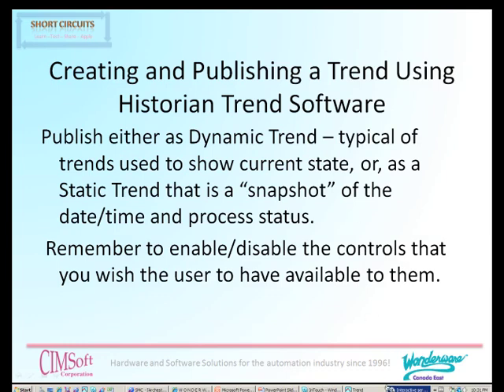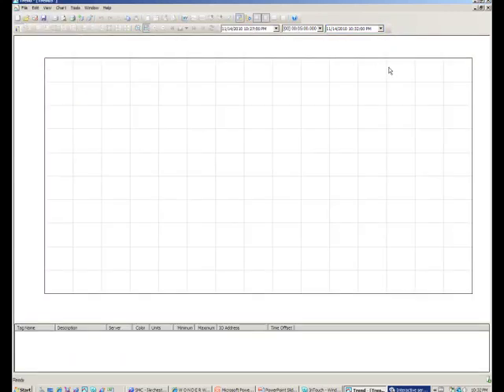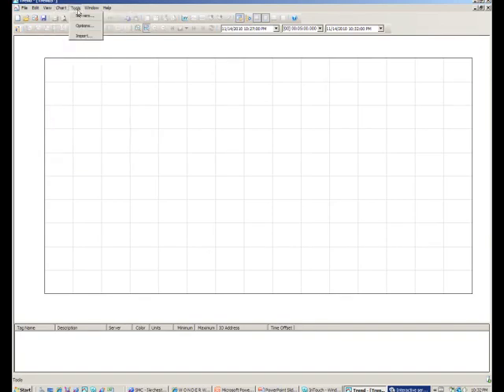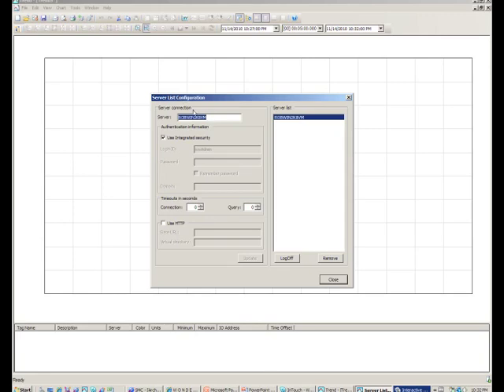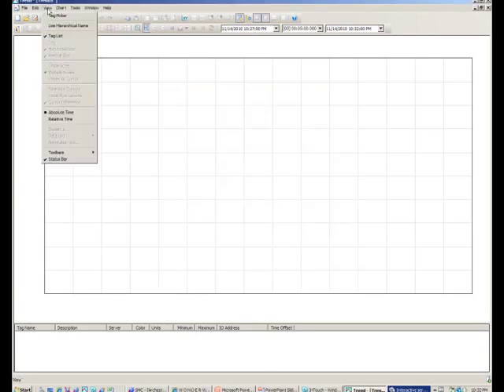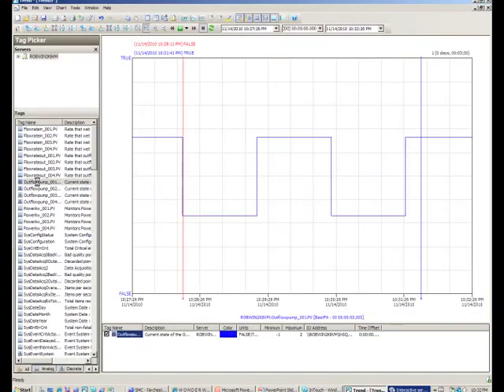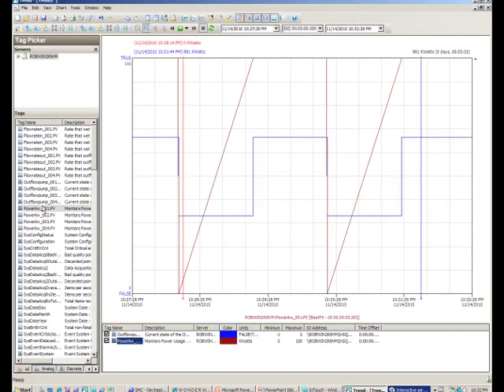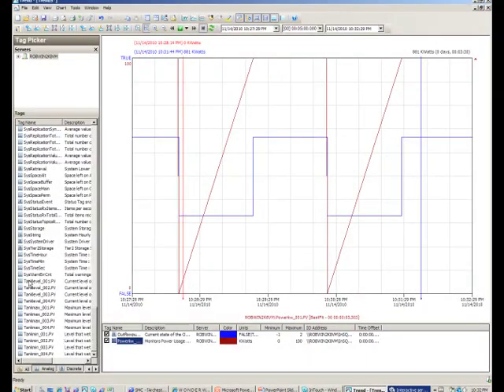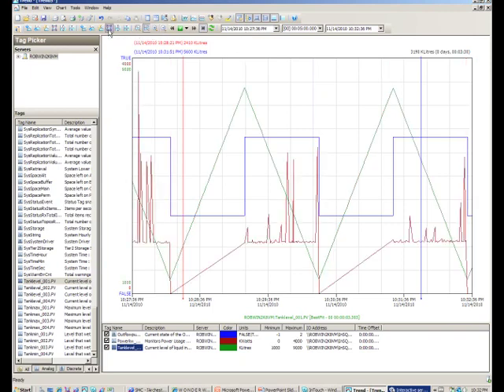To begin with what we'll do is we'll create a new trend so we'll say file new and what we need to do is we need to look at a few things here in order to do this. So we want to look at what servers we have available and we find out that we have the right server which is the one on this machine. We want to take a look at a few things such as the tag picker because we have the design. Now again we're going to use the same exact station so we'll put on the outflow pump from station 1 and we'll put on the power kW from station 1 which is the kilowatts of power being currently used. We'll also put the tank level on as we did the last time and now what we'll do is we'll scale it as we did just to make sure that we can see all the points that we need to see.